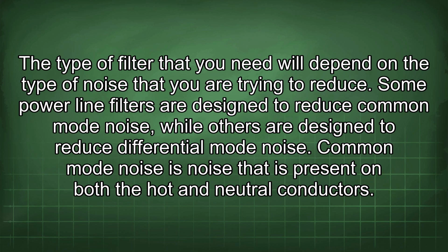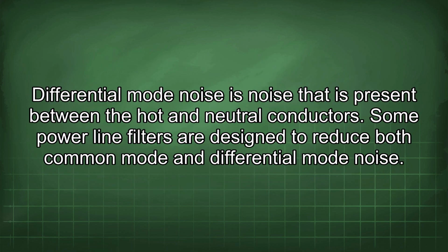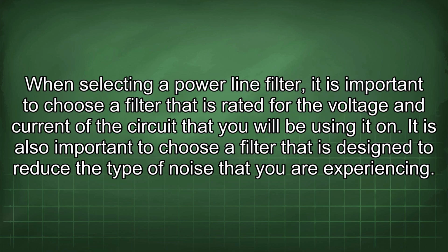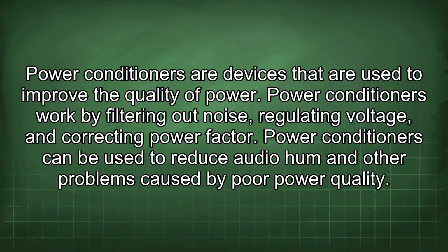Common mode noise is noise that is present on both the hot and neutral conductors. Differential mode noise is noise that is present between the hot and neutral conductors. Some power line filters are designed to reduce both common mode and differential mode noise. When selecting a power line filter, it is important to choose a filter that is rated for the voltage and current of the circuit that you will be using it on. It is also important to choose a filter that is designed to reduce the type of noise that you are experiencing. Power conditioners are devices that are used to improve the quality of power.